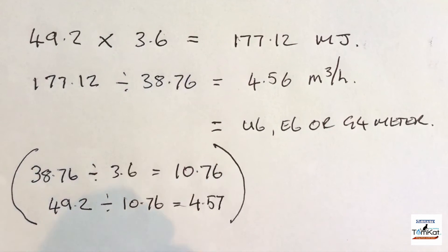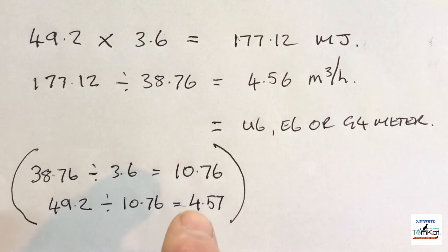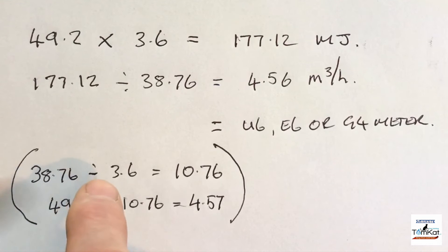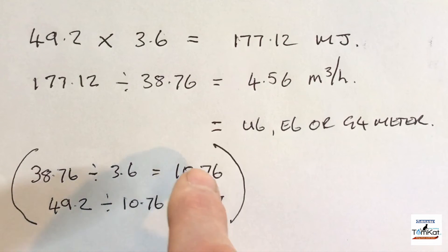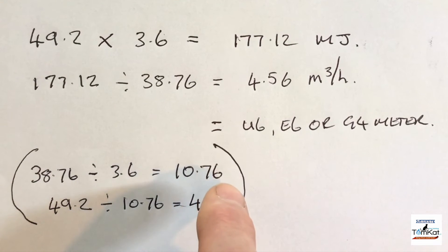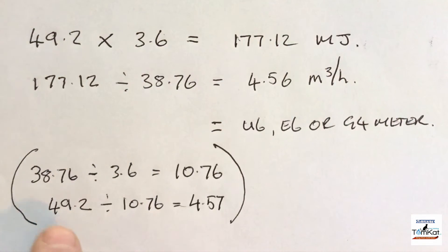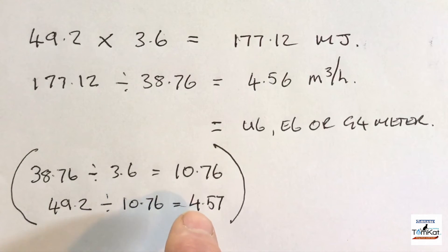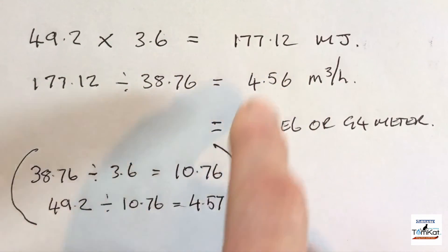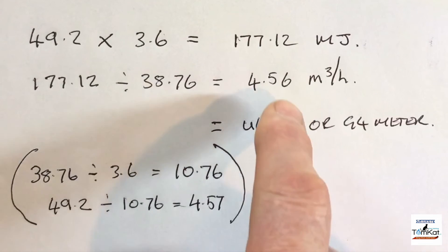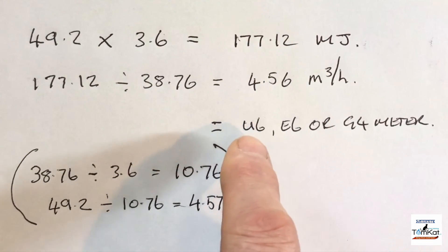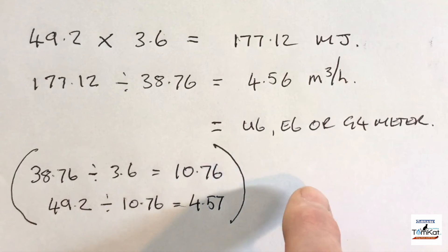For those who want a shortcut: divide 38.76 by 3.6 to get 10.76. Then instead of the full two-step conversion, simply take your diversity-adjusted kilowatts (49.2) and divide by 10.76, giving 4.57 m³/hr — only 0.01 different. You can still select a U6, E6, or G4 gas meter.